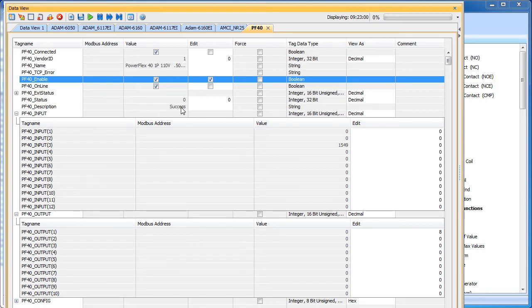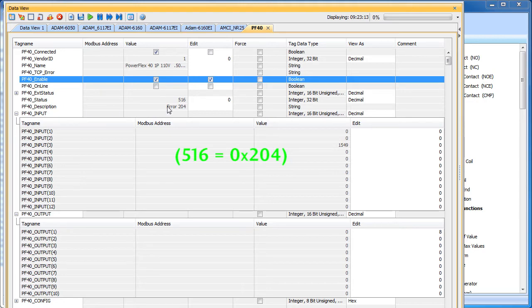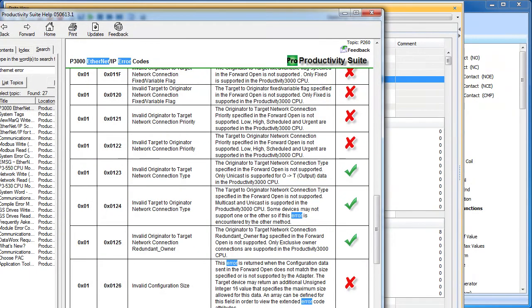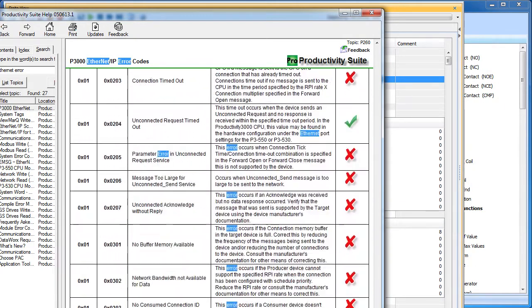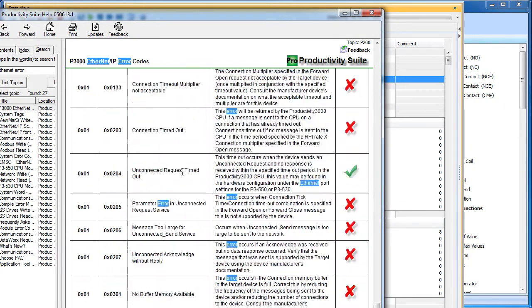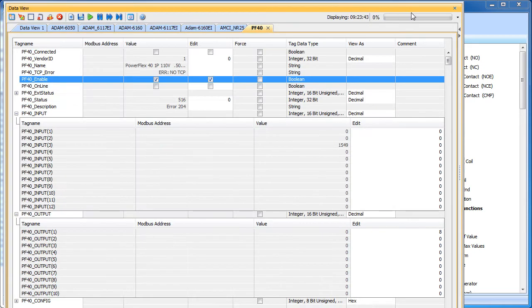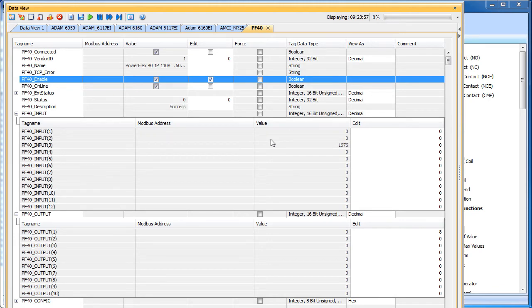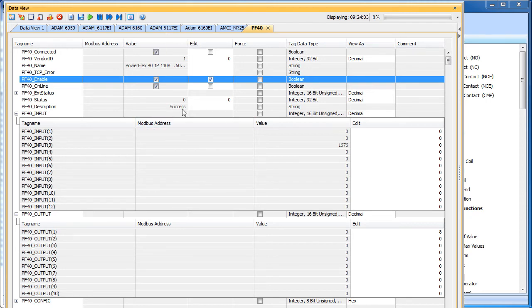Now just for the heck of it, I'm going to unplug the Ethernet cable and let's see what happens here. Well look, our status changed, we got a 516 error and the description says it's error number 204. Well, in the help file with the Productivity 3000 is this awesome table listing all the possible errors you can get with this thing. Error 204 says we have a timeout. Well, we know that, we just unplugged the Ethernet cable. So let me plug that back in and without doing anything, the Productivity 3000 automatically recognized that we regained that connection, reestablished the connection and we are back up and running. So, as you can see, having all these status tags is really, really handy when you need to debug what's going on with your system.